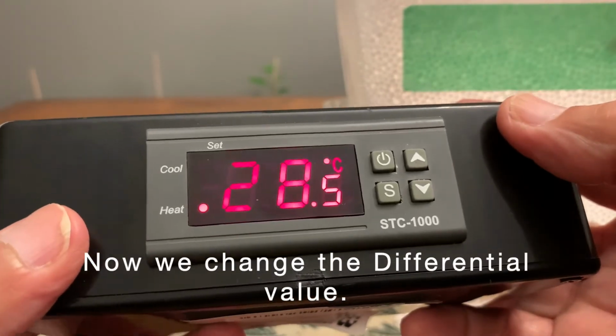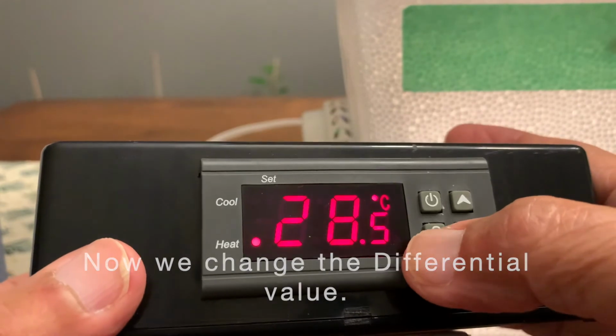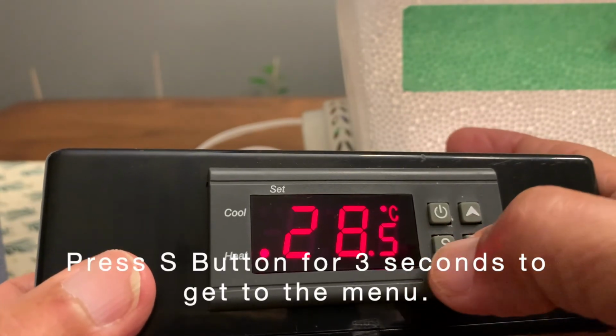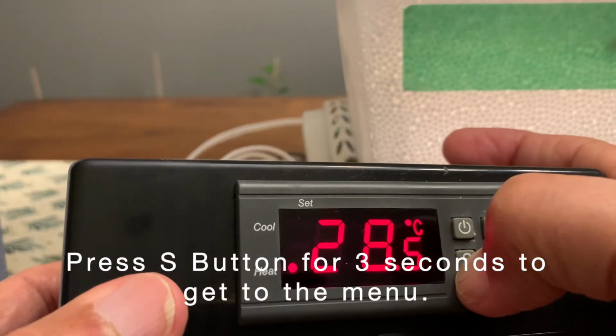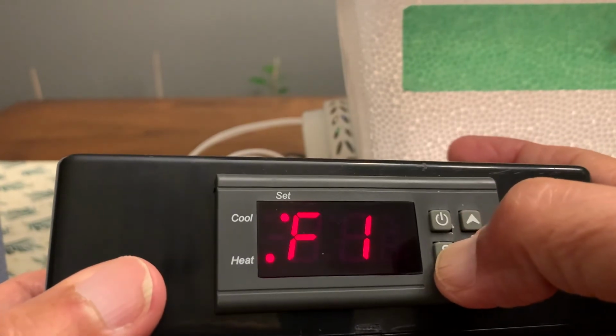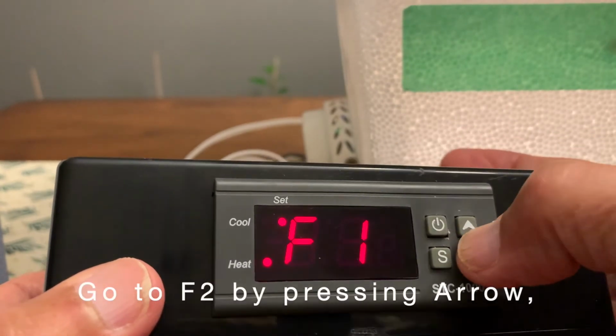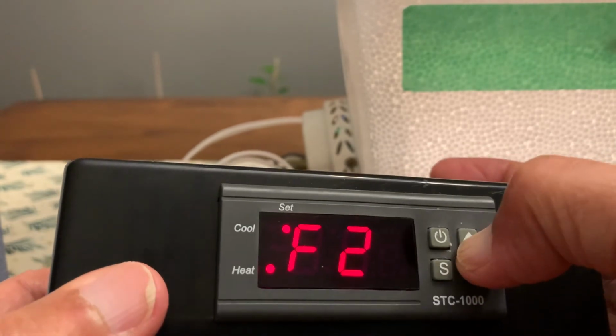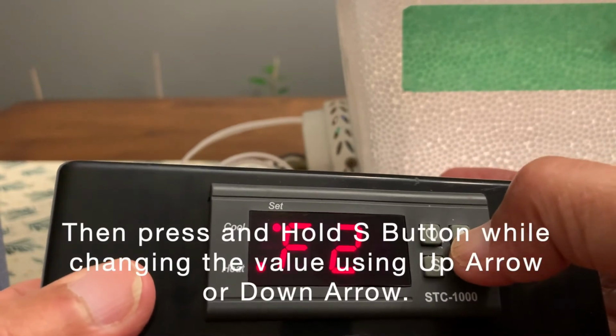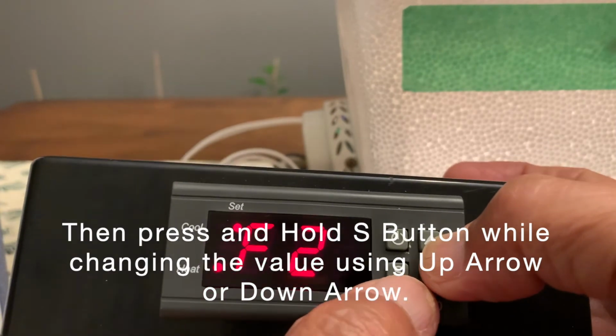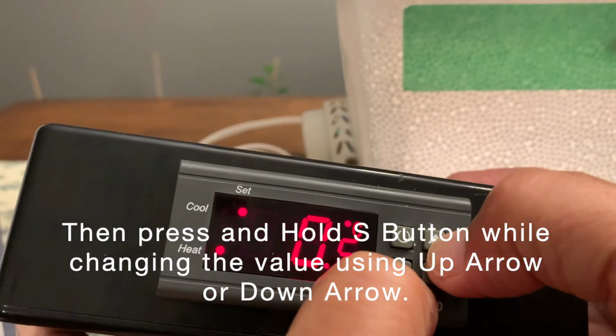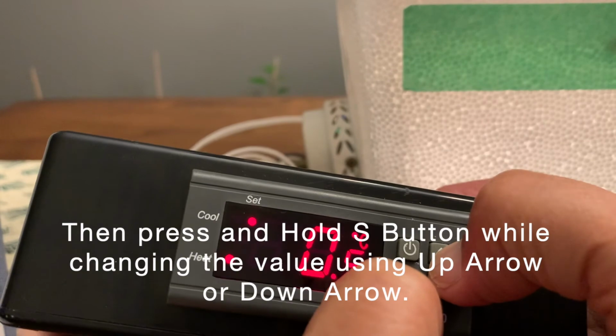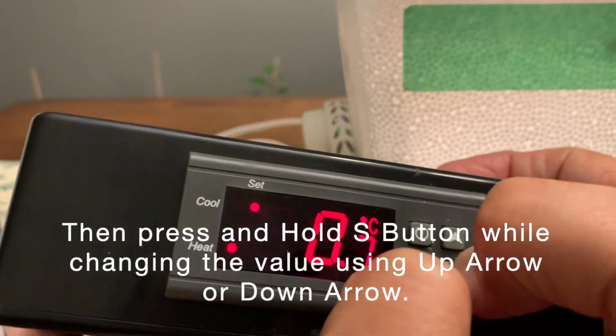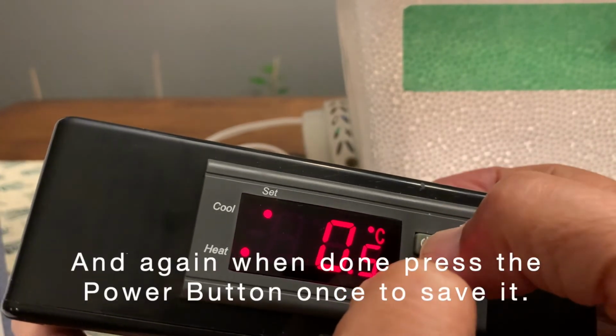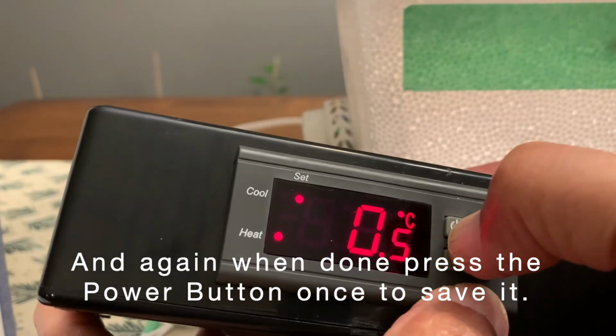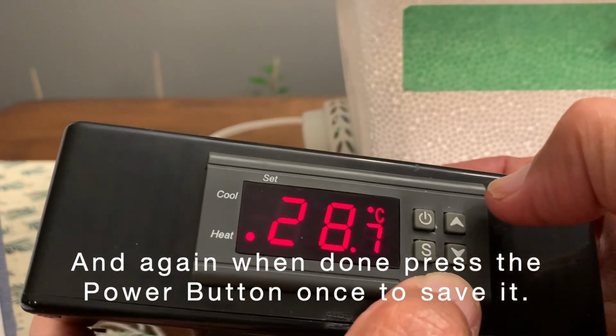Now we change the differential value. Press S button for 3 seconds to get to the menu, go to F2 by pressing arrows. Then press and hold S button while changing the value using the up arrow or down arrow. And again, when done, press the power button once to save it.